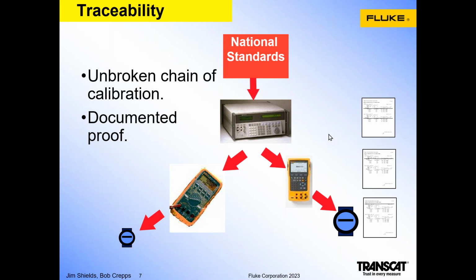Now that field device would then be the device the technician would take out in the field to calibrate process instrumentation. When the process instrumentation is calibrated, the performance of the device before it was adjusted is recorded. The performance of the device after it was adjusted, if necessary, is also recorded. The time, the date, and who did the work is also recorded and then documented on a record. So the point here is that there's an unbroken chain of documentation from the National Standards Organization right down to the documentation that covers the calibration of the field device that's out in the process making measurements.